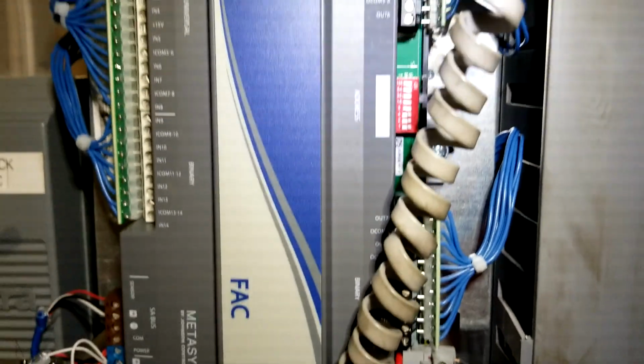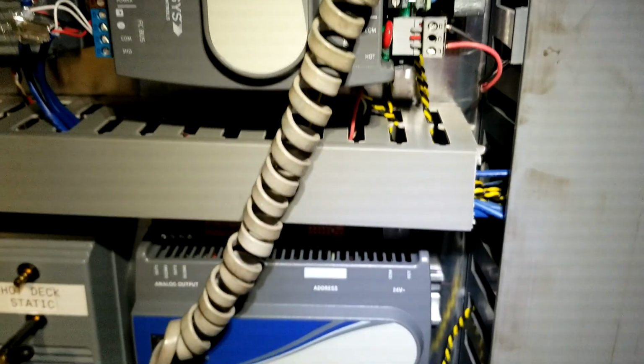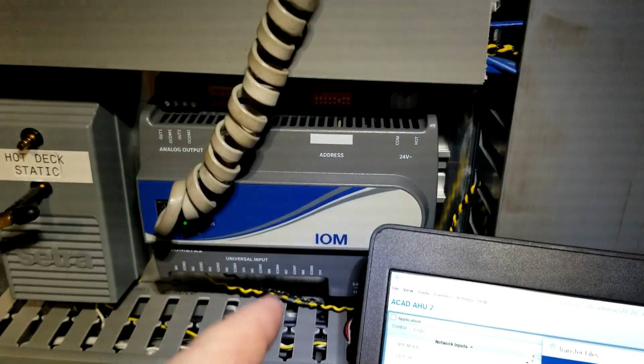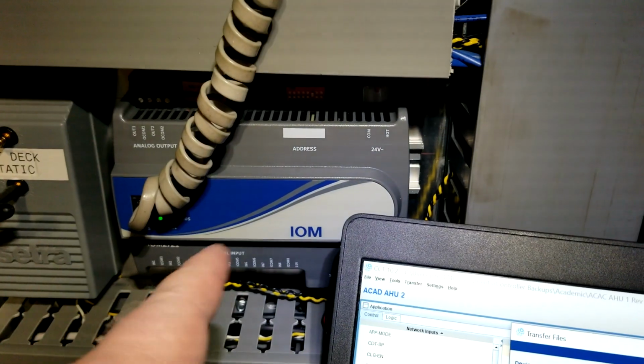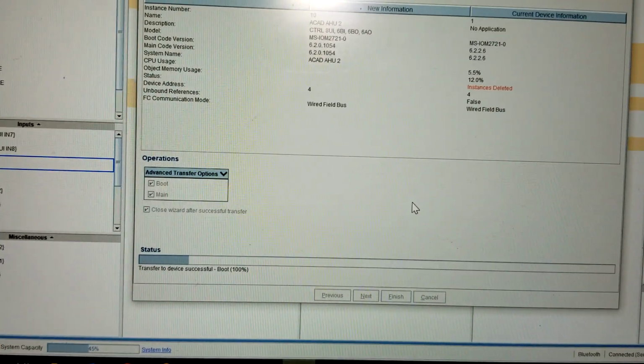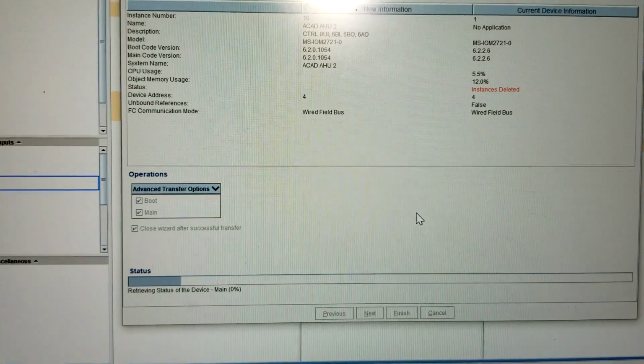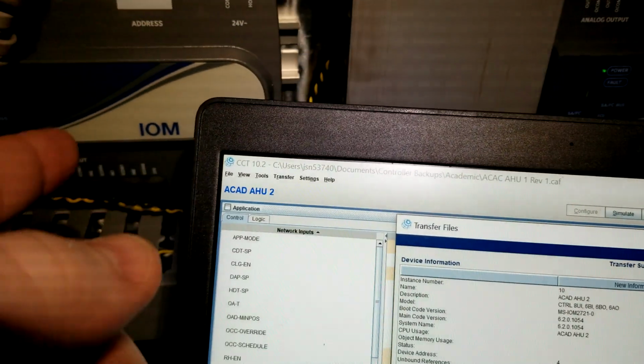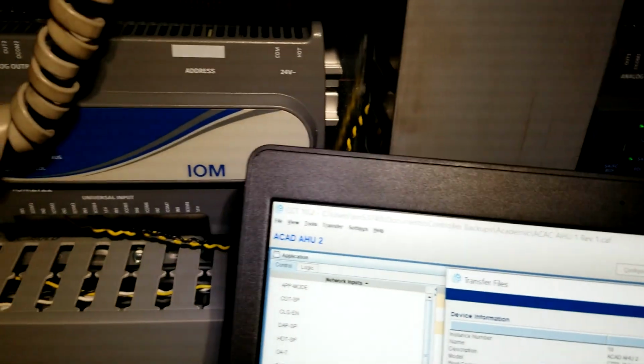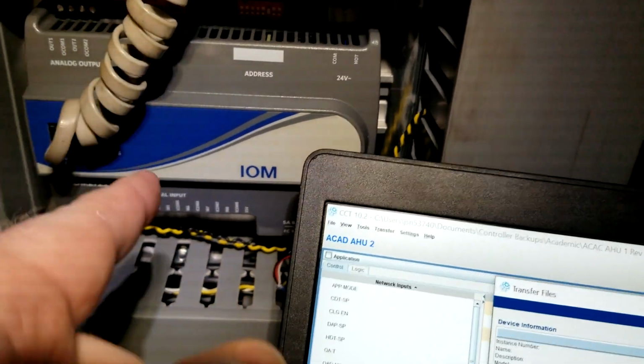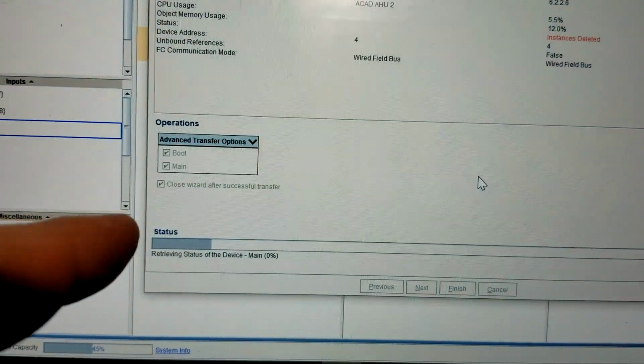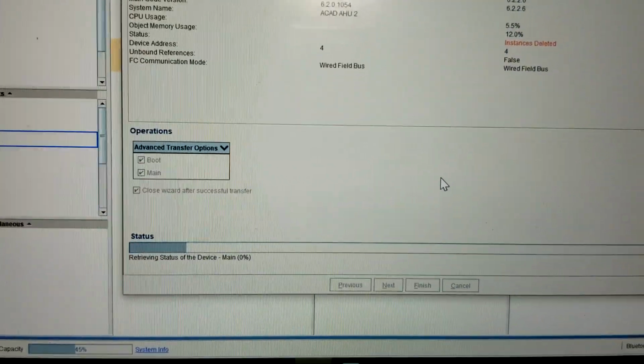Something you need to be aware of when you load the controller for the first time — you need to make sure you plug your adapter directly into the IOM. If you don't, you won't be able to load it; it'll give you a device exception error, because the IOM doesn't necessarily know how it needs to communicate. So plug directly into the IOM, push the boot and main code from your program, then go back to your main controller and push the program there as well.